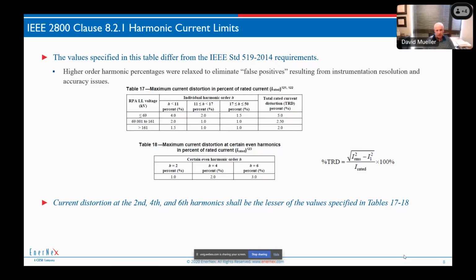What we have to do is meet the limits 95% of the time. We have to have a cumulative probability 95% level that meets the limits. So we can exceed the limits part of the time, but 95% of the time, the values that we record, we have to meet these limits, and these limits are in percent of rated current. So if it's a 200 megawatt plant, then perhaps we'll use that as our base rating to apply these percentages.